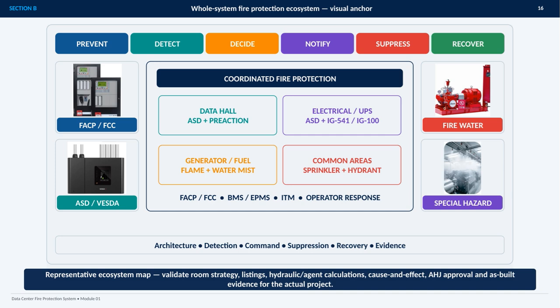The ecosystem also includes the FACP or FCC, ASD or VESDA, fire, water, and special hazard systems. These must connect with BMS and EPMS, ITM activities, and operator response. Finally, the design has to be validated through room strategy, listings, hydraulic or agent calculations, cause and effect, AHJ approval, and as-built evidence for the actual project.